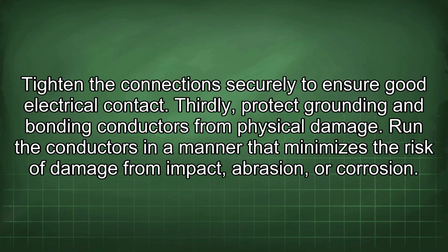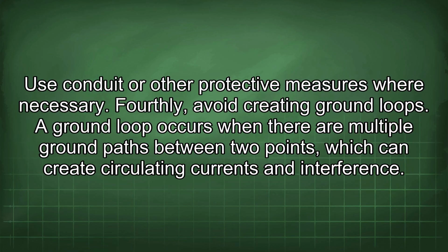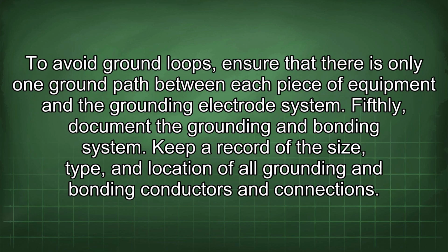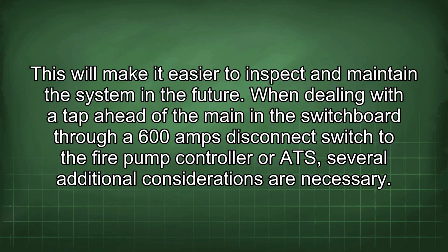Thirdly, protect grounding and bonding conductors from physical damage. Run the conductors in a manner that minimizes the risk of damage from impact, abrasion, or corrosion. Use conduit or other protective measures where necessary. Fourthly, avoid creating ground loops. A ground loop occurs when there are multiple ground paths between 2 points, which can create circulating currents and interference. To avoid ground loops, ensure that there is only one ground path between each piece of equipment and the grounding electrode system. Fifthly, document the grounding and bonding system. Keep a record of the size, type, and location of all grounding and bonding conductors and connections. This will make it easier to inspect and maintain the system in the future.